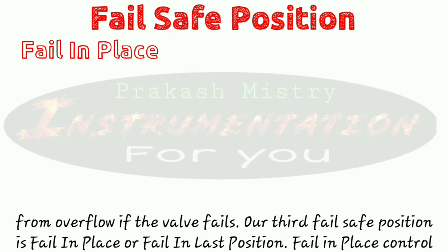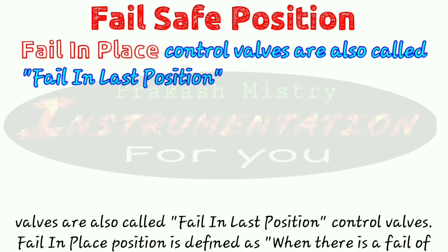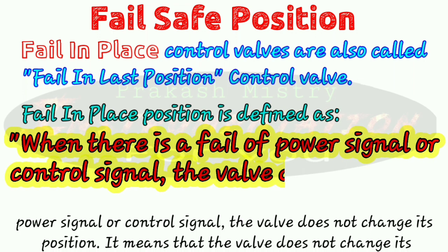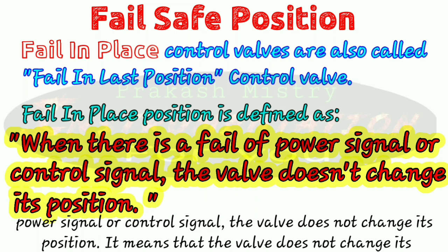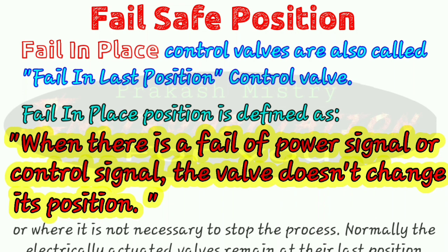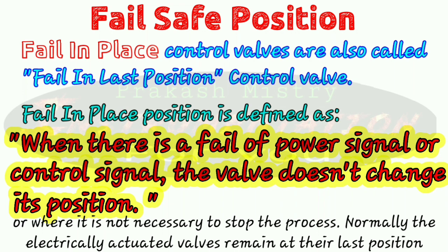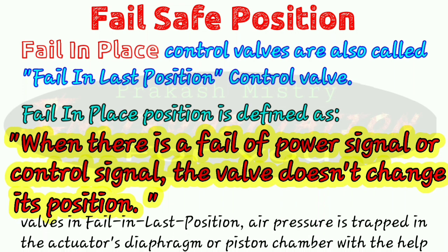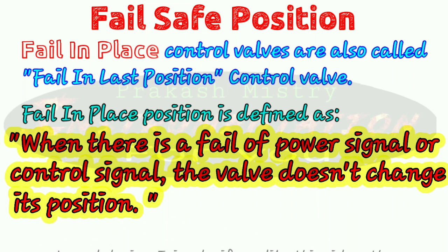The third fail-safe position is fail in place, also called fail in last position. Fail in place is defined as when there is a failure of power signal or control signal, the valve does not change its position. The valve does not react when power is lost. These fail in place positions are useful when the process cannot be shut down or where it is not necessary to stop the process. Normally, electrically actuated valves remain at their last position when the power signal fails. For pneumatic or hydraulic valves, air pressure is trapped in the actuator's diaphragm or piston chamber with the help of an external device to achieve fail in last position.